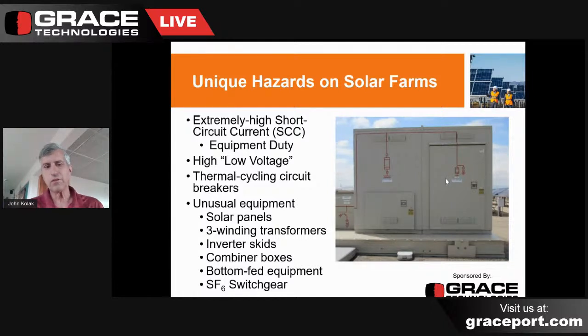3-winding transformers, transformers that share a primary winding. So you have a high voltage winding and 2 low voltage windings that feed discrete parts of the farm. That's a piece of equipment for which employees or electrical workers would require additional training. Inverter skids are also a piece of equipment on a solar farm that requires special training. Workers may be fluent, for example, with inverters and pad mount transformers, but here we have them put together on the same skid. So we have an alternating current side and a direct current side of an inverter system, each having unique hazards. Some of them we will cover in this presentation.